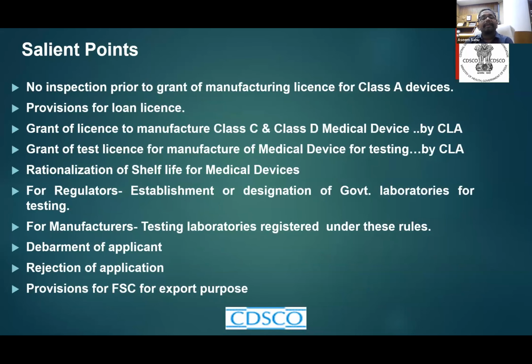For low risk devices, we have made a provision that no prior inspection is mandatory. The application will be granted once it is submitted within a particular time, and they can manufacture. However, within a certain period, the inspection is to be carried out to verify the quality management system. Provision of the loan license we have made in the Medical Device Rules, where the loaning firm can avail the facility of manufacturing for their own product by way of the loan licensing system.